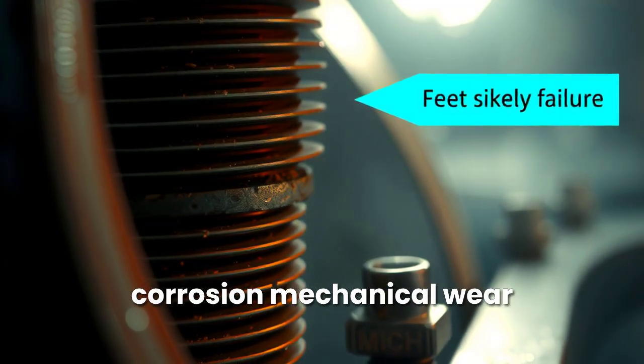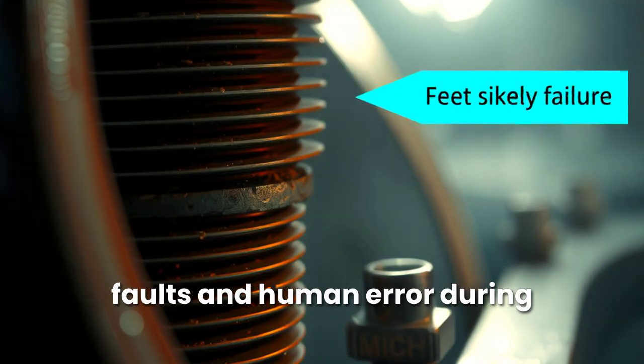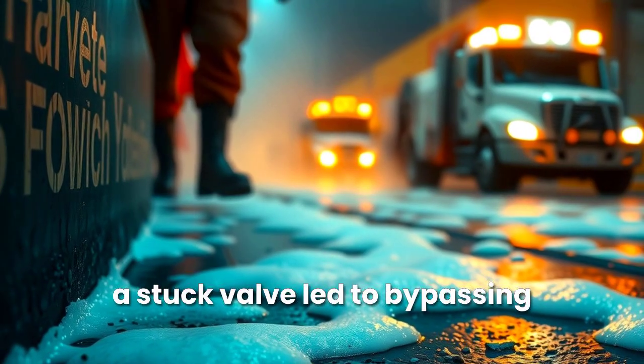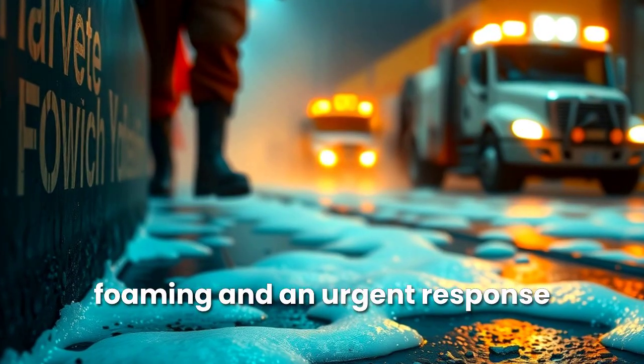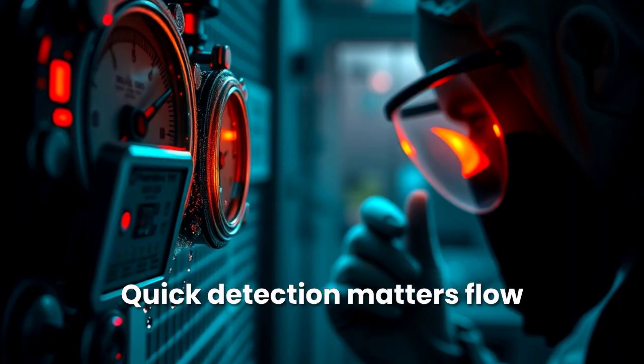Common failure causes include corrosion, mechanical wear, packing failure, actuator faults, and human error during isolation, each leaving clues to follow. Watch this real incident where a stuck valve led to bypassing treatment, visible surface foaming, and an urgent response from operators. Quick detection matters.